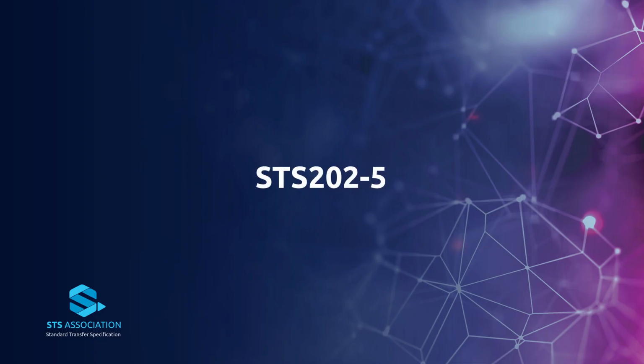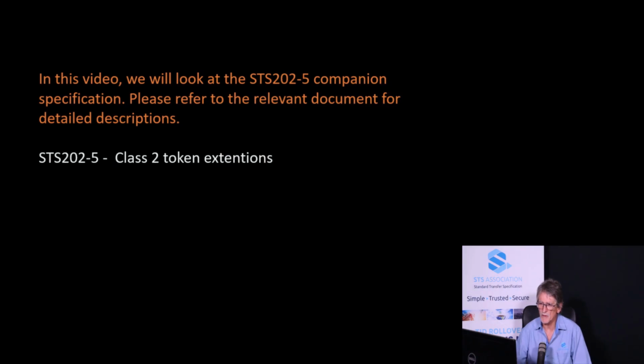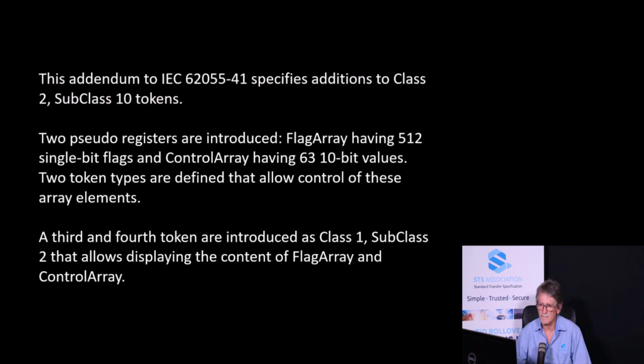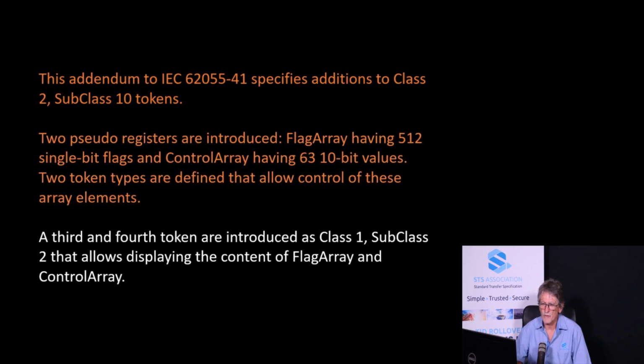In this video, we will look at the STS202-5 companion specification. Please refer to the relevant document for detailed descriptions, and that document is STS202-5 Class 2 token extensions. This addendum to IEC 62055-41 specifies additions to Class 2 Subclass 10 tokens. Two pseudo-registers are introduced, a flag array having 512 single-bit flags and a control array having 63 10-bit values. Two token types are defined that allow control of these array elements.